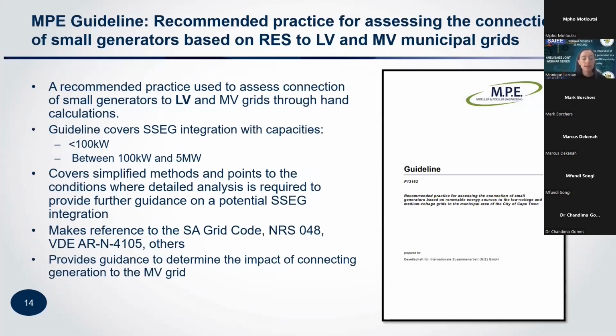Okay, then the other guideline that I just quickly want to go through is the MPE guideline. As mentioned, it was developed by a German consulting firm, but it did make reference to the South African grid code and NRS and VDE documentation. It makes recommendations on LV and MV grids where the NRS only focuses on LV, and it covers a set of integration considerations for generators smaller than 100 kilowatts, and then also makes recommendations for generators between 100 kilowatts and 5 megawatts. And then it points to conditions where detailed analysis might be required and what the municipalities would need to do in this instance. And then also importantly, as I've mentioned, it also gives guidance on MV connections where NRS 097 only focuses on LV connections.